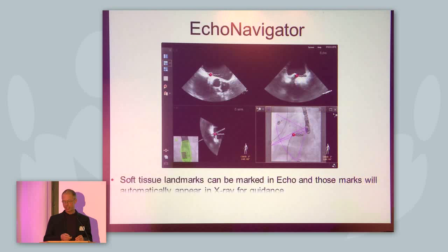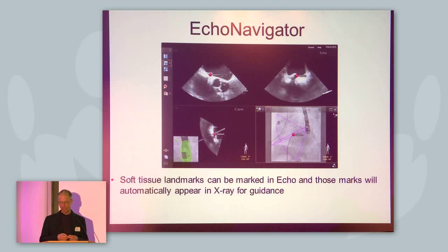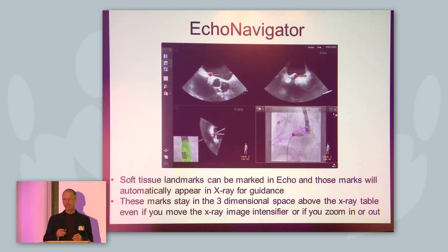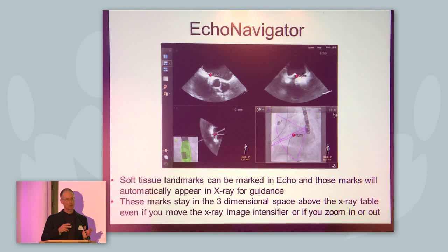Here you can see an example: soft tissue landmarks can be marked in echo, and those marks will automatically appear in the x-ray for guidance. These marks then stay in the three-dimensional space, regardless of whether you move the table or the patient, or whether you remove or change the position of the image intensifier — these marks always stay in the three-dimensional space.